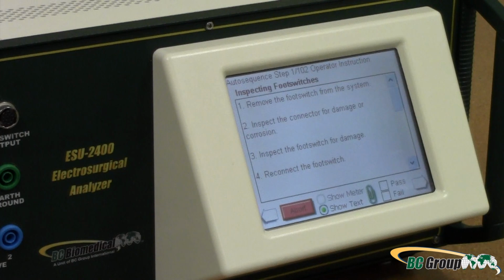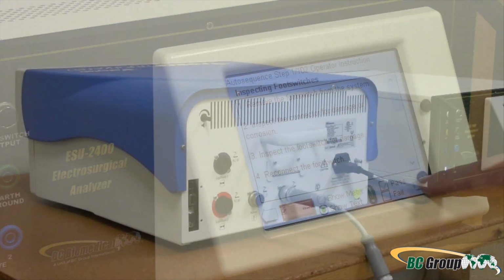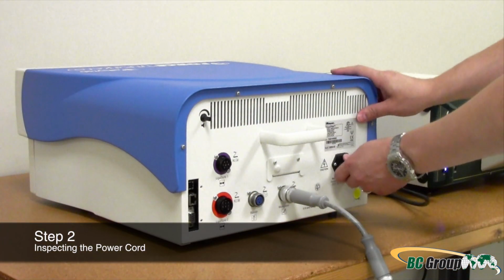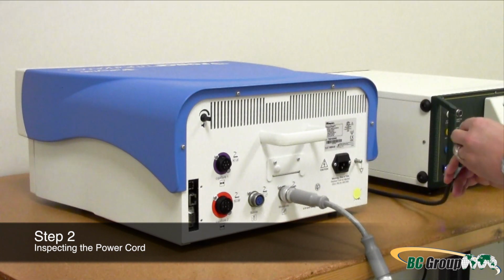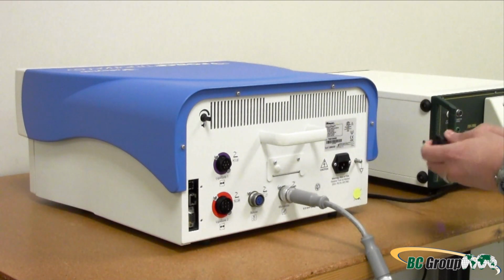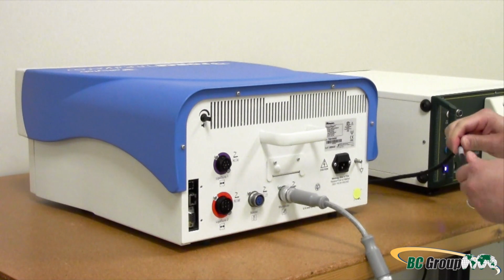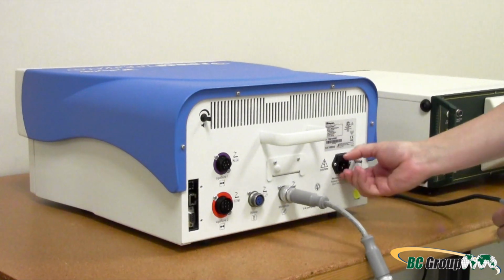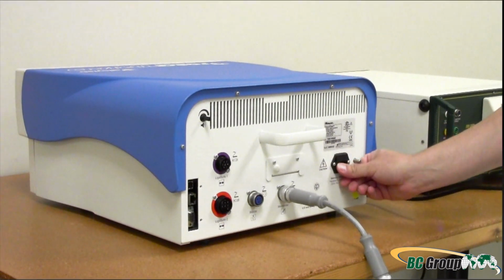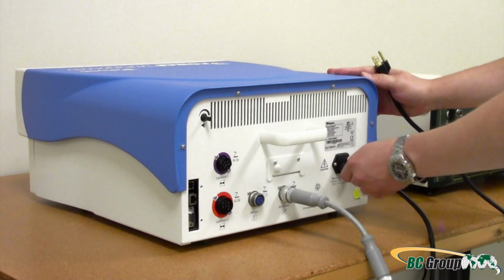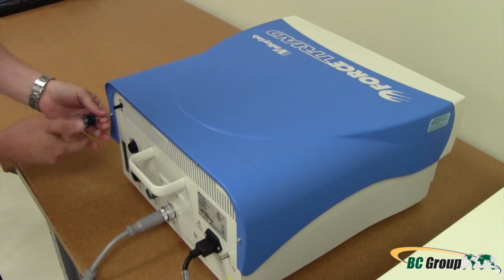Remember, after each step you should review all of the instructions displayed on the ESU-2400. If the device under test passes, check the box next to pass and touch the arrow at the bottom right of the screen to advance to the next step. Step 2. Inspecting the power cord. Turn off the system. Remove the power cord and ensure that it is unplugged from the wall receptacle. Inspect the power cord for damage. Reconnect the power cord.